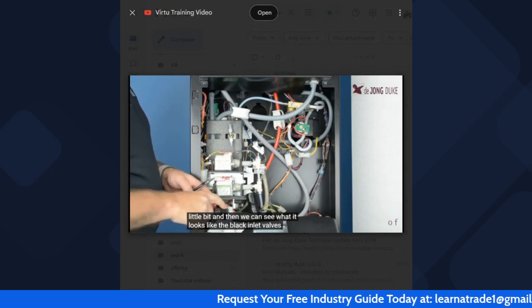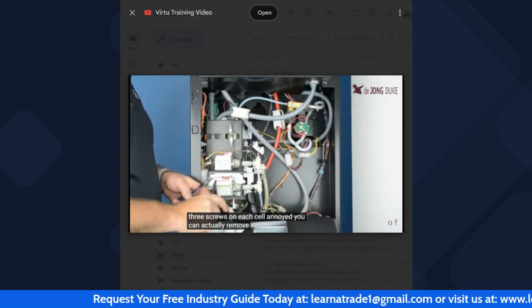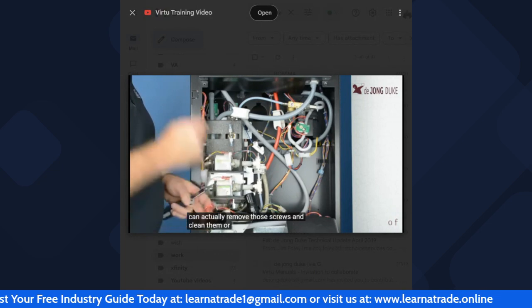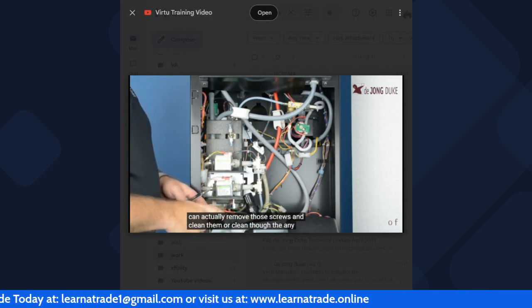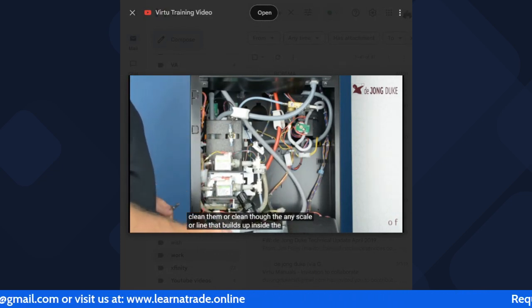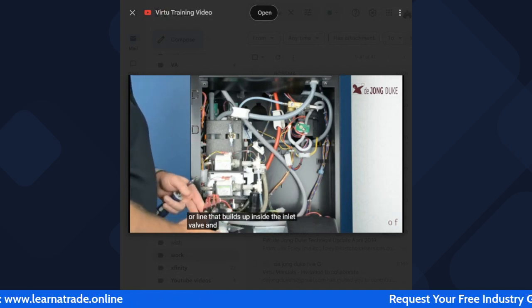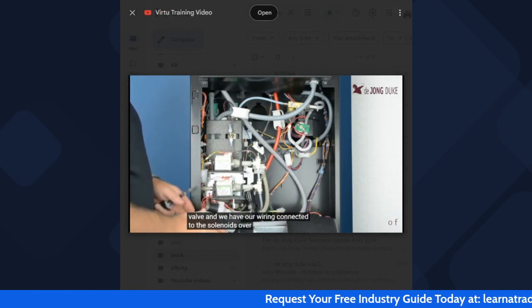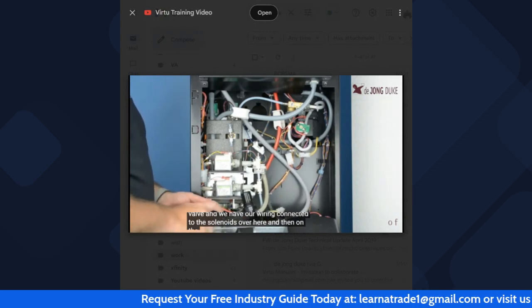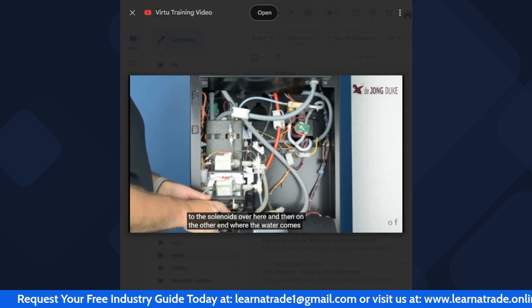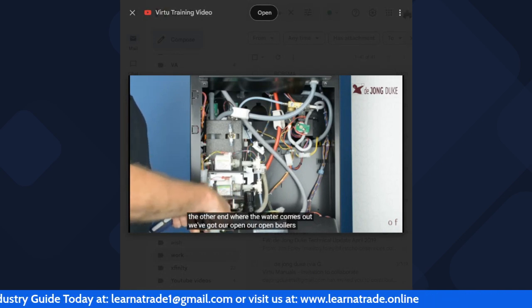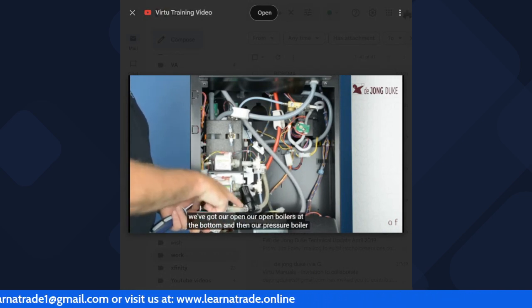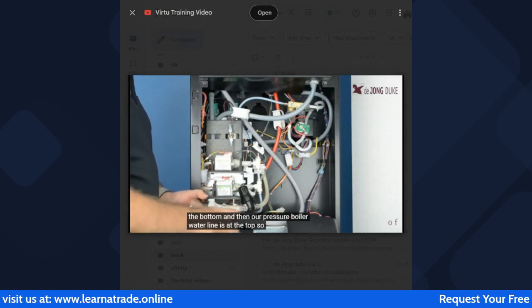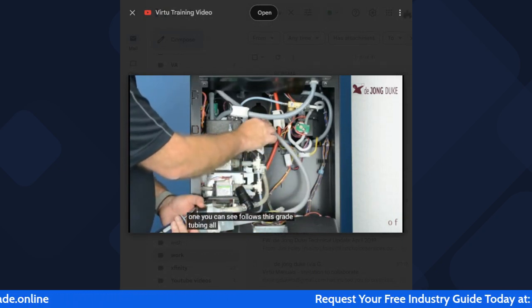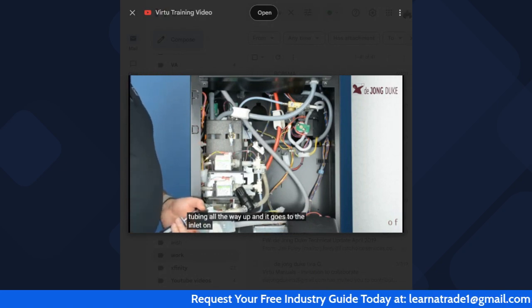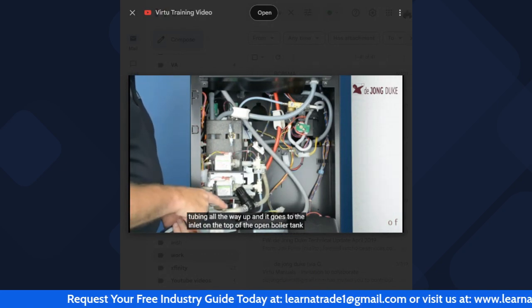The black inlet valves have 3 screws on each solenoid. You can actually remove those screws and clean any scale or lime that builds up inside the inlet valve. And we have our wiring connected to the solenoids over here. And then on the other end where the water comes out, our open boiler is at the bottom, and our pressure boiler water line is at the top. So the bottom one, you can see, follows this gray tubing all the way up, and it goes to the inlet on the top of the open boiler tank.